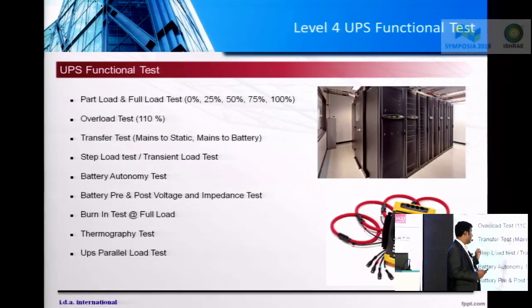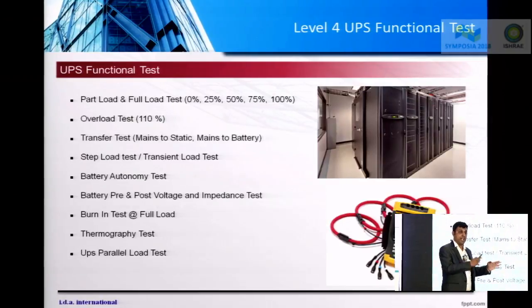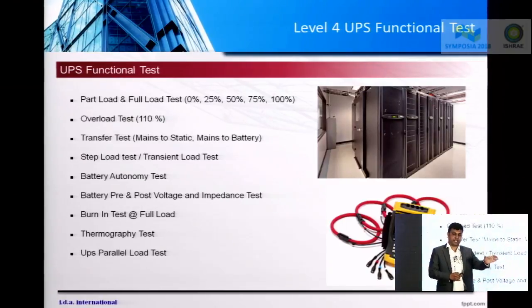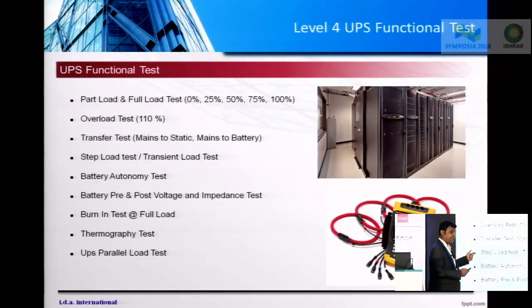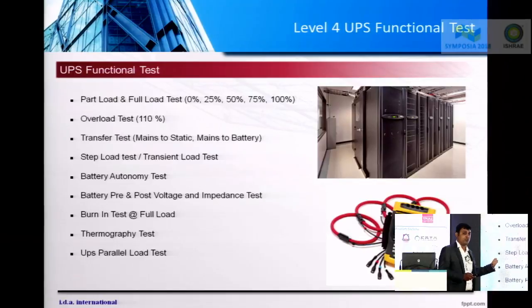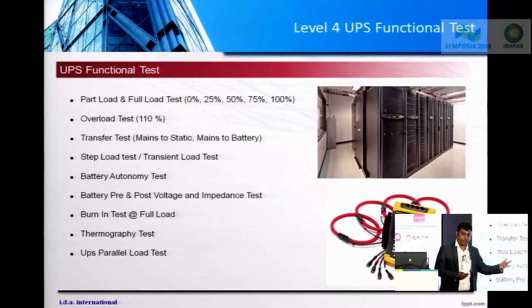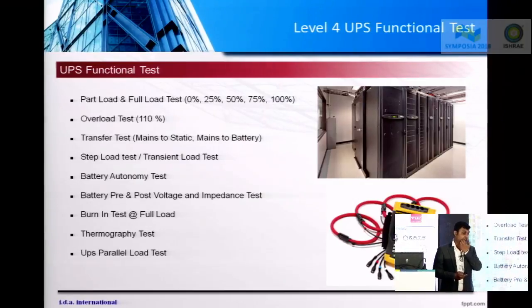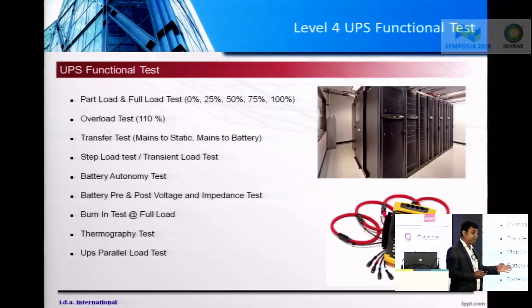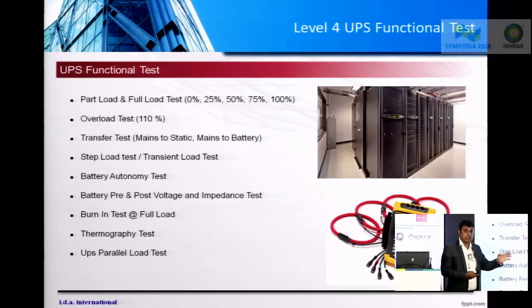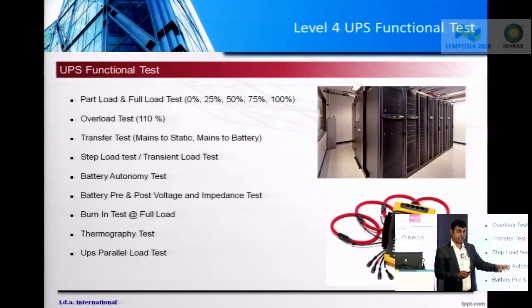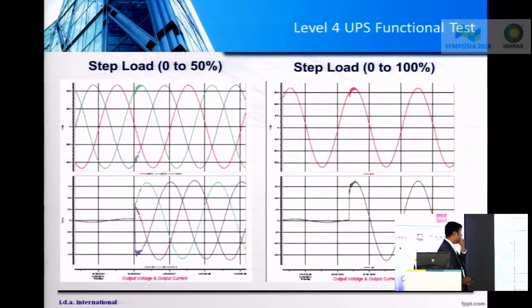which means the UPS, we can transfer from mains to static bypass, from static bypass to mains, mains to battery, battery to mains. That has to be verified. Step load test or transient test, battery backup test, pre and post battery voltage and impedance verification, burn-in test at full load condition, thermography, and UPS parallel load test. Now let's understand it one by one.